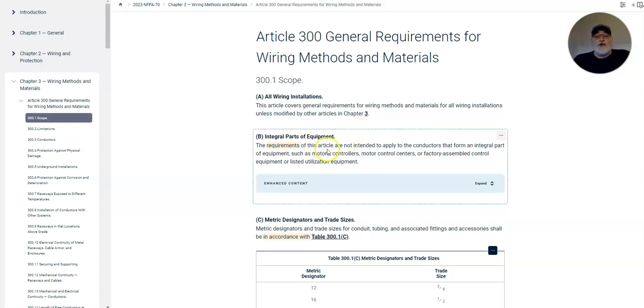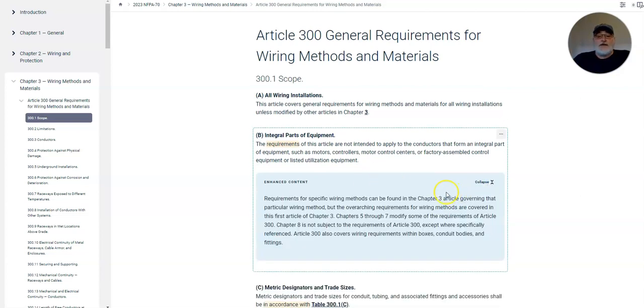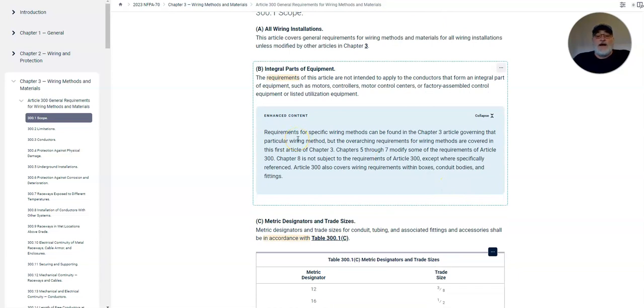In Part B, integral parts of the equipment. The requirements of this article are not intended to apply to the conductors that form an integral part of equipment, such as motors, controllers, motor control centers, or factory-assembled control equipment or listed utilization equipment. Basically, if it comes from a factory and somebody else built it and you're installing it, their wiring doesn't fall under the NEC. The NEC picks up from where you make a connection to the equipment, supplying power to it.